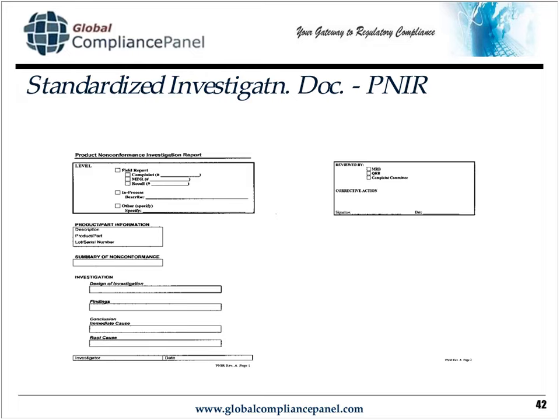And then after the conclusion is completed and the investigator signs their name, one of your interdepartmental bodies should review this record of investigation. It's either going to be your material review board, if it's an incoming component. This company has a quality review board, which meets quarterly to look at quality nonconformances, or a complaint committee, which usually meets monthly to look at complaints. And it's not the investigator that determines corrective action. It should be an interdepartmental body.